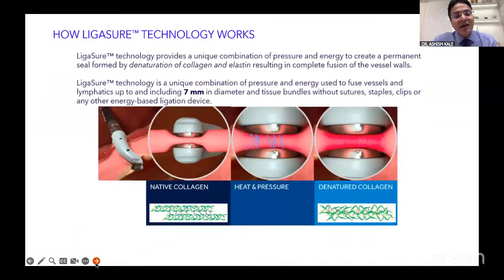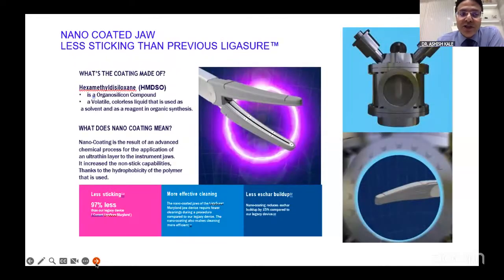When you see the LigaSure between the two jaws, you can see in this figure the native collagen. When the heat is passed between the two jaws along with the pressure, the collagen tissue is disrupted, and you get a cutting effect, with the nano-coated jaw. This is the new bipolar device, with the same principles, where you have a curved Maryland jaw, coming with the same LigaSure technology. These jaws have non-sticking particles, so the jaw will not be sticky.